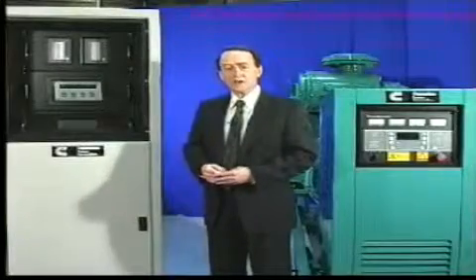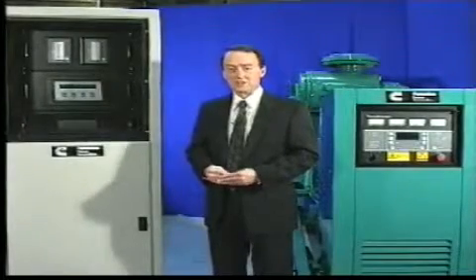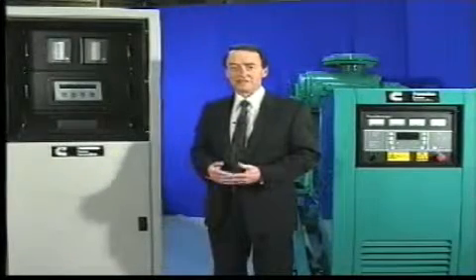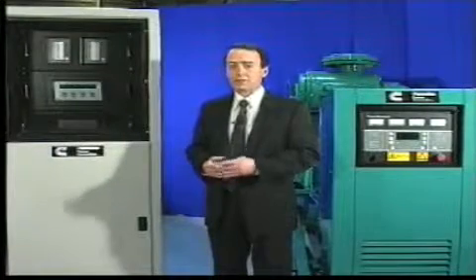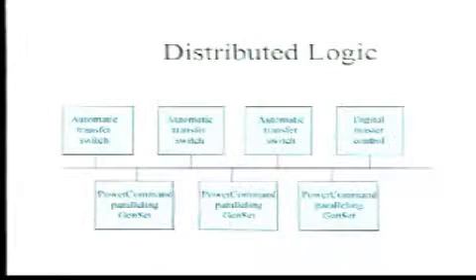That's a win-win situation. Because each Power Command genset contains all paralleling controls and capabilities, the usual maze of controls, relays and fuses is eliminated. The gensets communicate directly with the master control, but they're not dependent on it. Rather than a conventional master-slave design, Power Command paralleling uses distributed logic architecture. So each genset continues to be fully functional if other parts of the system, even the master control, should fail.